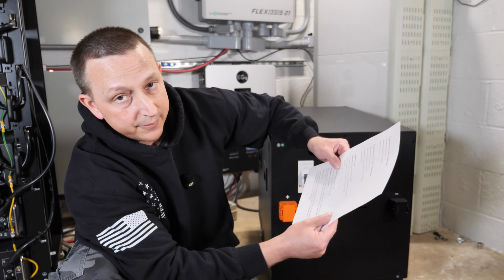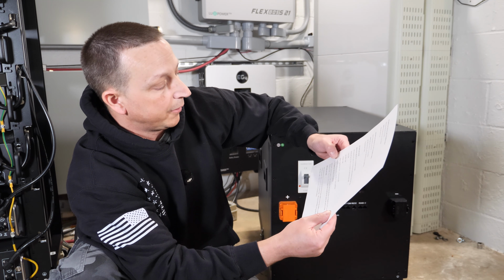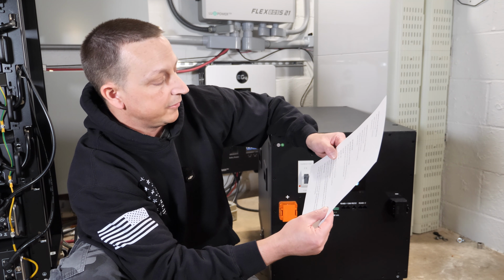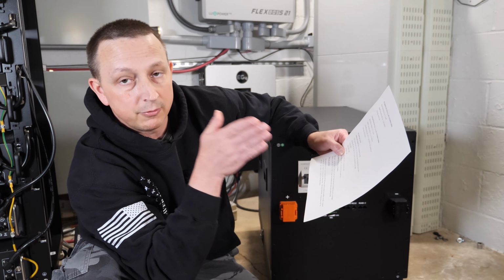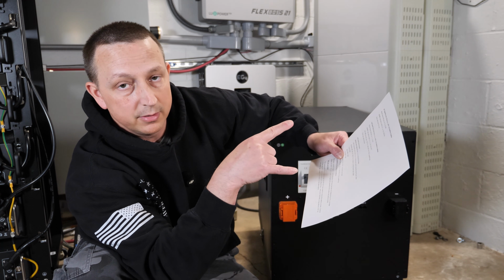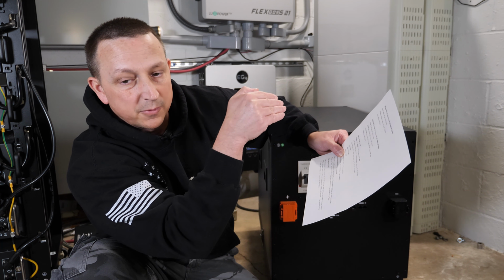The bus bar after the fuse was 194. The breaker was around 120, basically right in the center. I know there were 2 little hot spots where the bus bars connect.